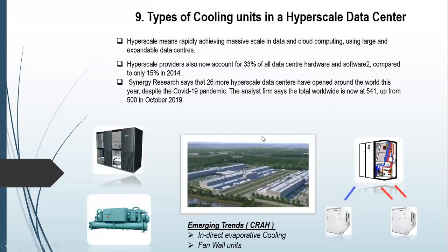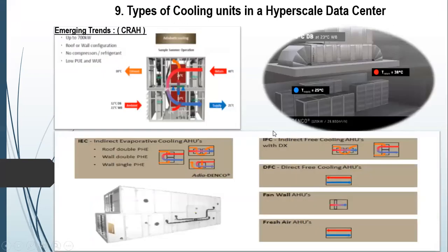Now going to the hyperscale, we spoke on the hyper server room. What are the cooling units which go into the hyperscale, which go into the server room? The hyperscales are basically large data centers, or cloud computing which is scalable. We had close to, I think, 500 hyperscales, but with the current situation and digitization, the hyperscales are also increasing. I think you all read the news of large hyperscalers which are investing in India. So what goes into the hyperscale? Of course, the CRAC units, chilled water connected, which can also be seen, called the PAHU units, along with the chiller. But the emerging trends in these large hyperscales, keeping a check on the PUE and COP, are computer room air handling units called indirect evaporative cooling and fan wall units. So what are these units? Let's look at this.